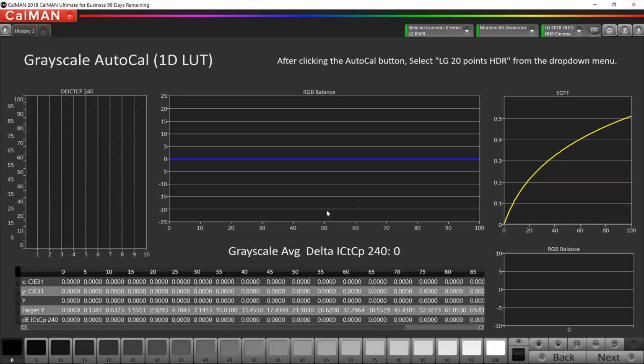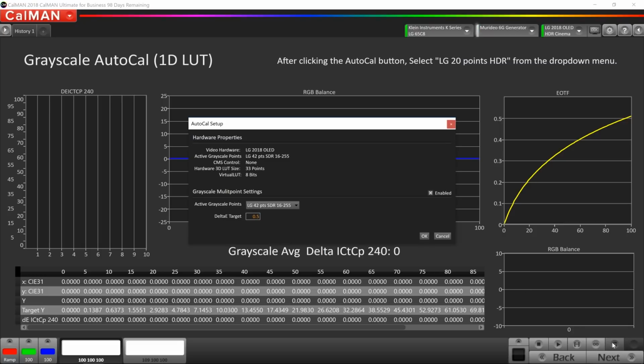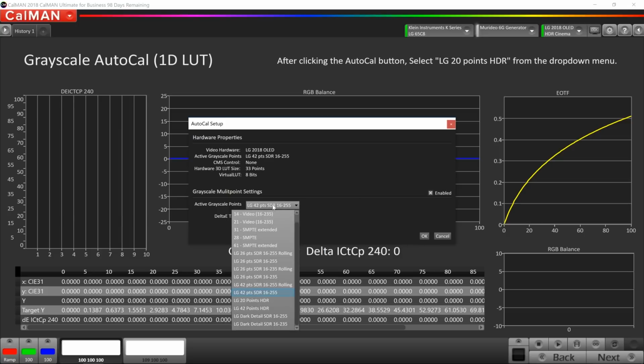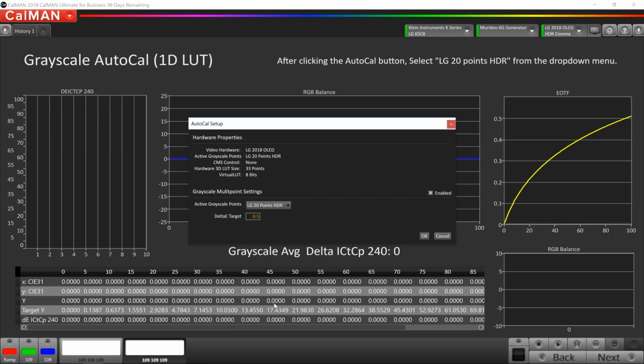Okay, first thing we're going to do is the grayscale AutoCal. This is similar to what we did in SDR. We need to change the amount of points we're going to calibrate. Let's do the 20-point HDR. You could do the 42 if you wanted to. That's okay. We're just going to do the 20 today. And we're going to keep the delta errors pretty low. I'm going to keep that set to 0.5.